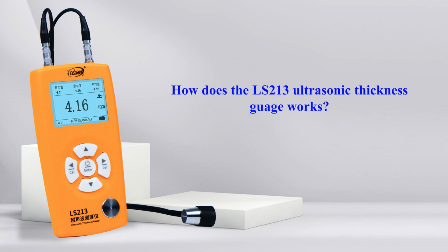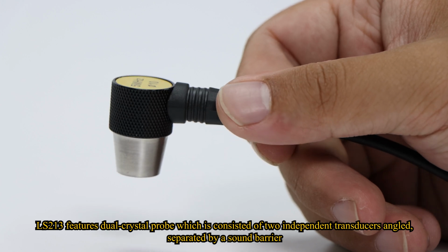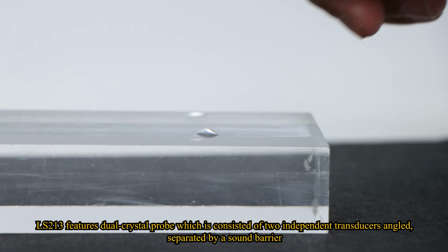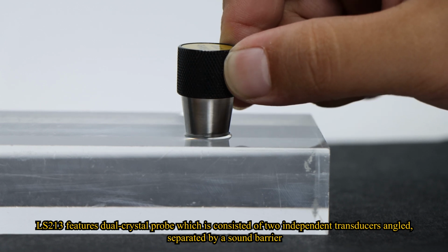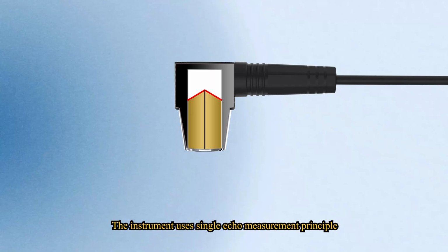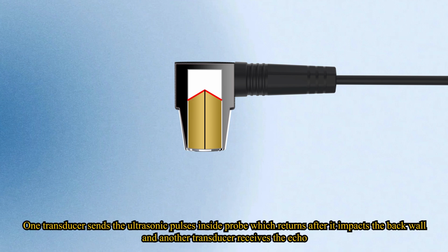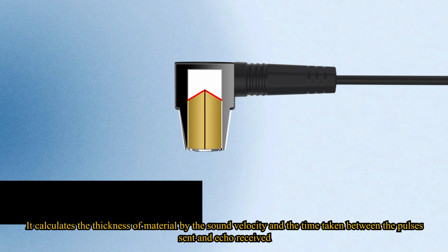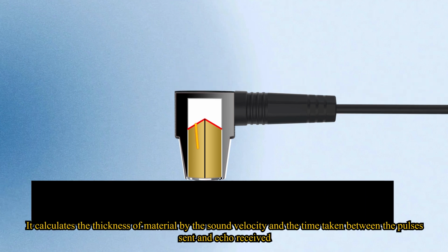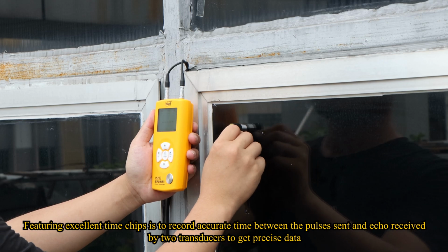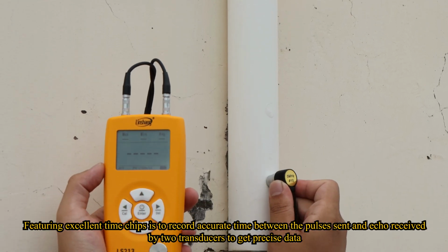How does the LS213 Ultrasonic Thickness Gauge work? The LS213 features a dual crystal probe, which consists of two independent transducers angled and separated by a sound barrier. The instrument uses the single echo measurement principle. One transducer sends the ultrasonic pulses inside the probe, which return after they hit the back wall, and another transducer receives the echo. It calculates the thickness of the material from the sound velocity and the time taken between the pulse sent and the echo received. Excellent time chips record the accurate time between the pulse sent and the echo received by the two transducers to get precise data.